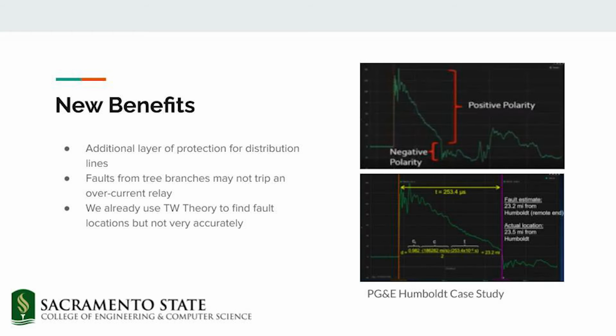This method of protection will also work whether the distribution line is energized or not, because the ultrasound wave is added to the line externally from generation. Additionally, it is operating at a much higher frequency than what our electricity runs at, so reading something like 60 Hz on our meter will not be something to alarm us. With ultrasonic technology on the line, it will be obvious to us when there is any break in the line and where it is, regardless of how much current is on it.